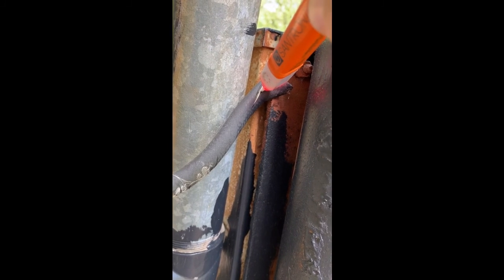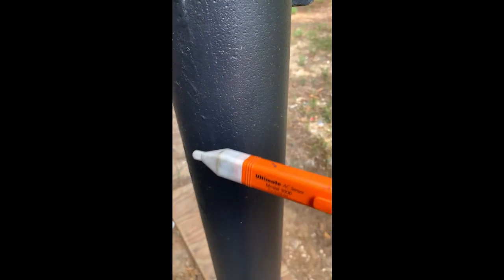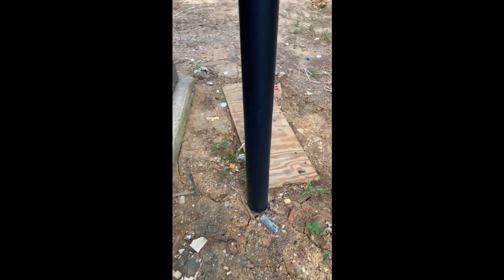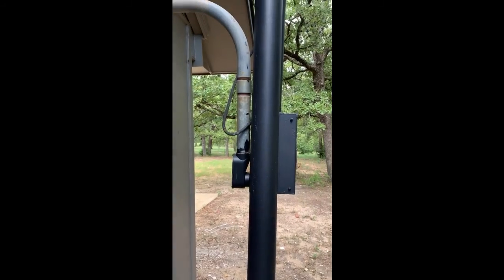Now this is very hot, the meter box is hot, and this pole is hot. So that could be very dangerous for kids. It could be very dangerous for animals that would come over and just rub up against it. This pole is hot, so we're going to recommend that they fix this.